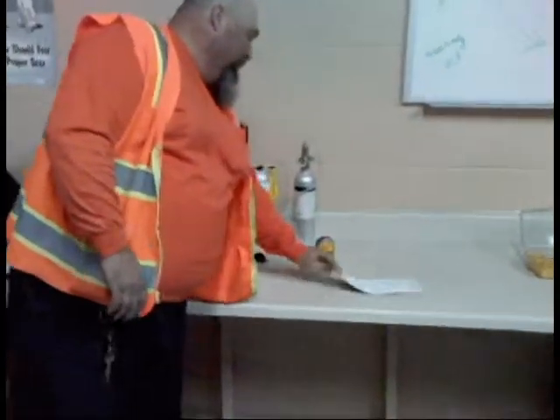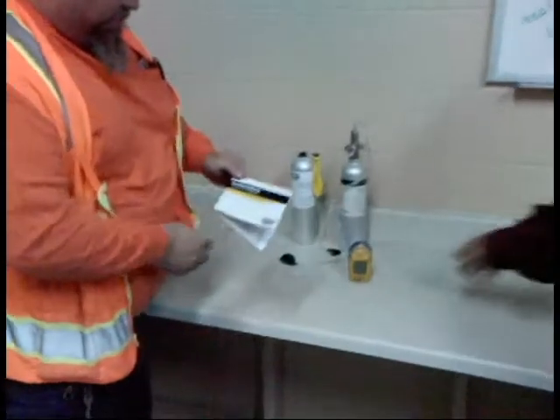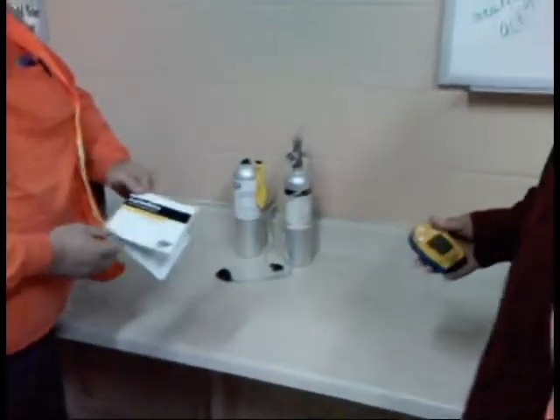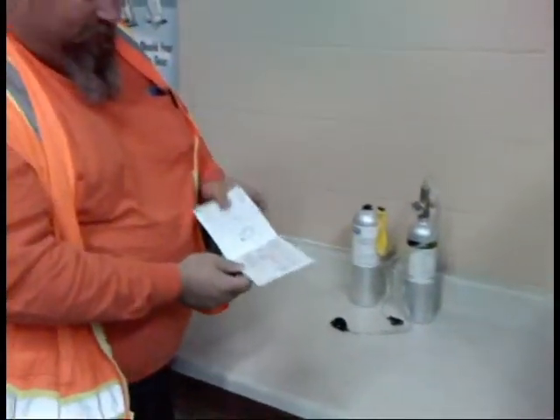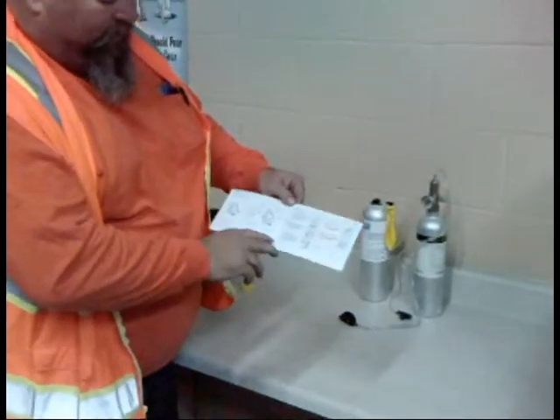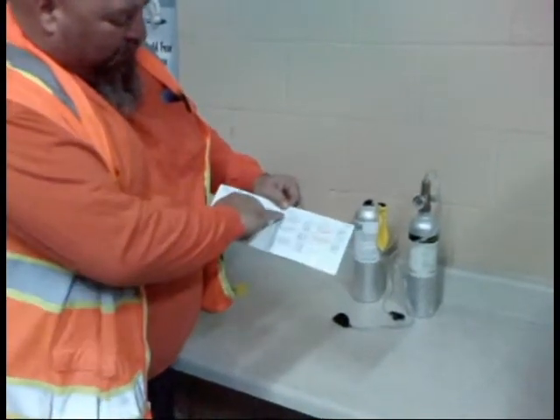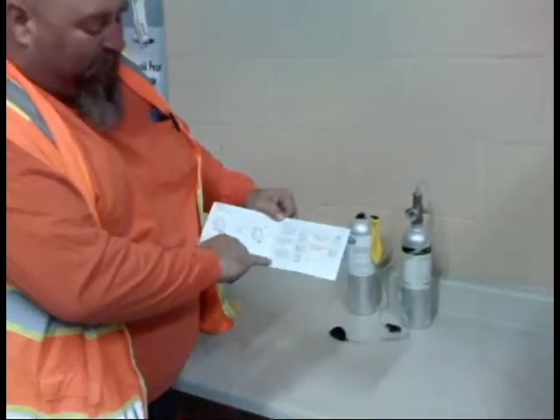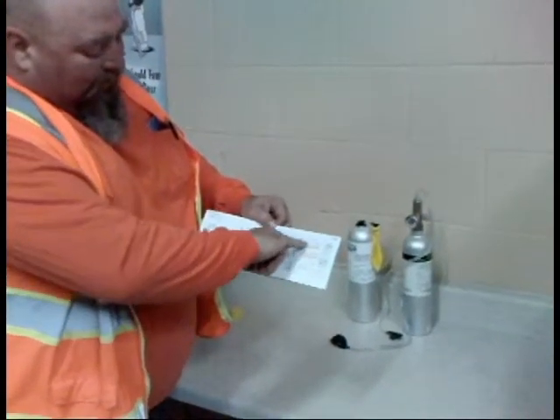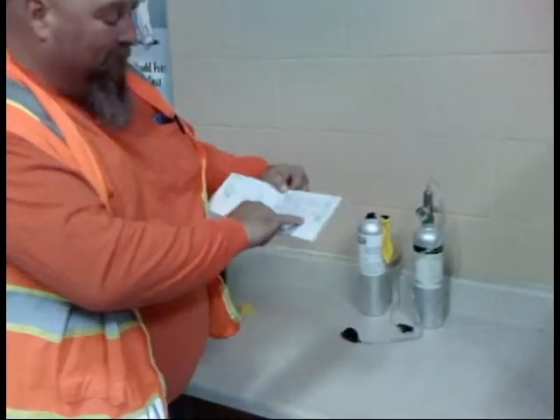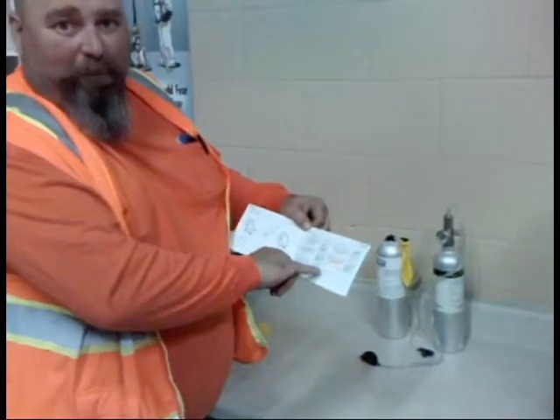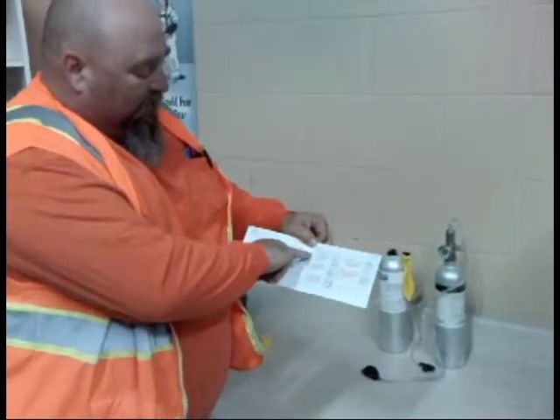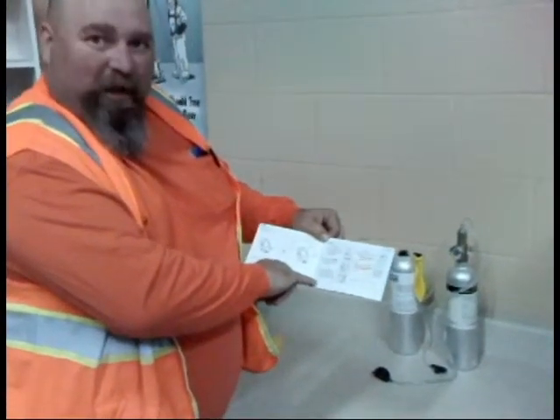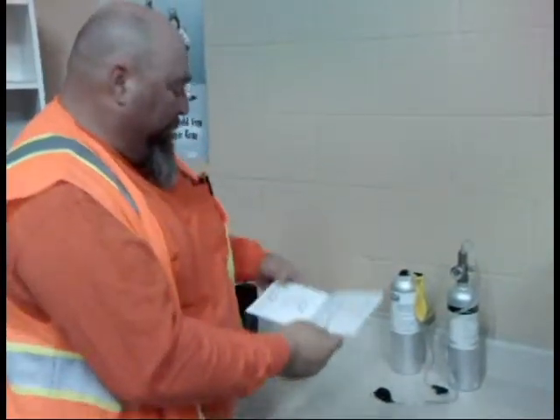When you're calibrating, all these sniffers come with a manual here, a quick reference guide that shows you the steps in calibration. What we're doing here is a simple three-step process. It goes into step 4 and 5, which is resetting the values. We're not going to do that. All we do is the first 3 steps, which is calibration of the sniffer.